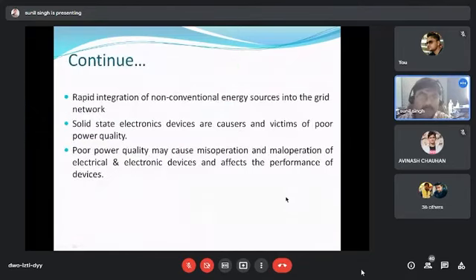Another important issue is the rapid integration of non-conventional energy sources into the grid network. As we know, nowadays we are integrating solar power stations or solar distributed generation into the grid. So it may also create a new problem, known as power quality. Maybe harmonics, under voltage, over voltage, or power factor problems, and all other problems we are facing. Harmonics is also a very important power quality issue, and because of harmonics, misoperation of the devices may occur.